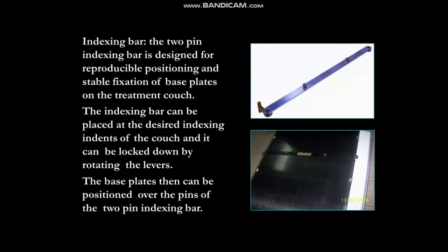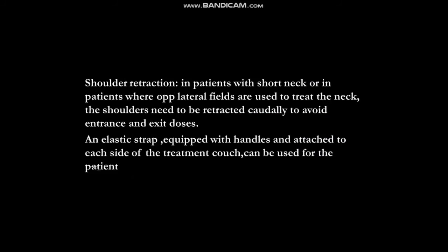Indexing bar. The two-pin indexing bar is designed for reproducible positioning and stable fixation of base plates on the treatment couch. The indexing bar can be placed at the desired indexing indents of the couch, and it can be locked down by rotating the levers. And the base plates can be positioned over the pins of the two-pin indexing bar.